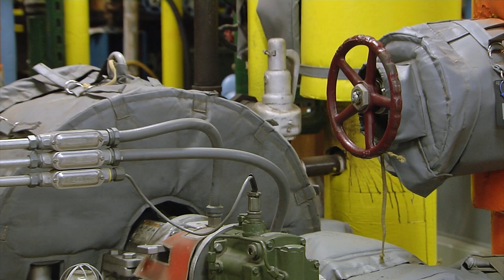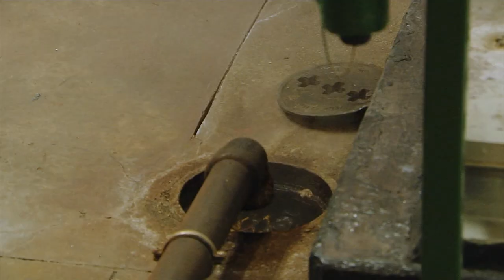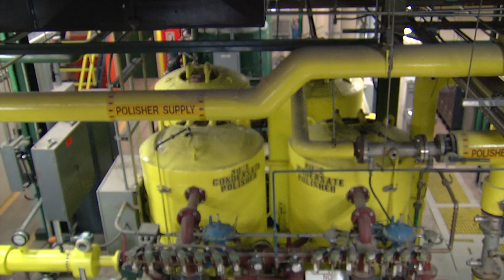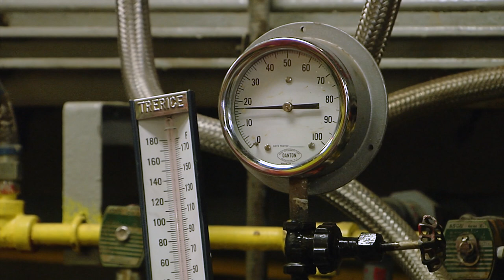So, Sal, how many buildings does this plant supply heating and cooling for? How much of an impact are we talking about? Well, the campus is about 6 million square feet with several hundred buildings, and this plant heats approximately 4 million square feet and cools about 2.5 million square feet. We send out steam at 220 pounds per square inch, which comes back as condensate and gets reheated into steam again, and chilled water is sent out at 42 degrees and comes back at about 55 degrees.